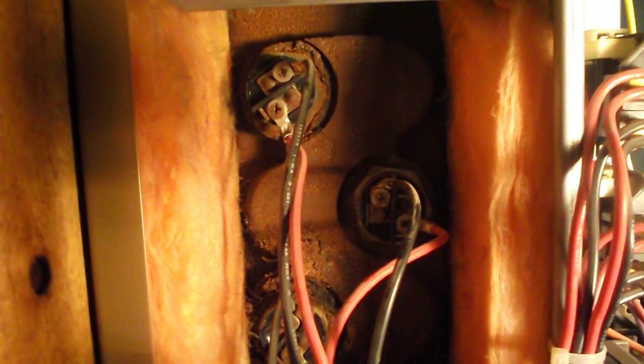And also in here, let's leverage the opportunity to have a look at some of these elements. The top two are the high current or high power elements. They had a resistance of 6 ohms, and then the bottom were the lower wattage elements at 13 ohms.